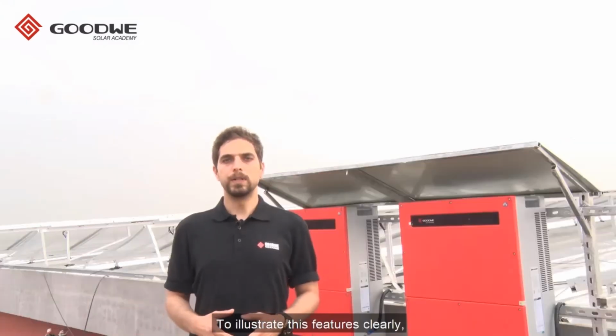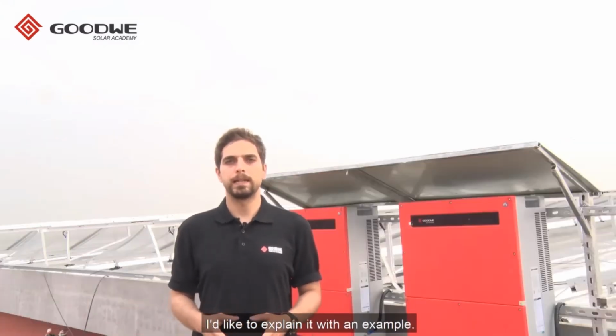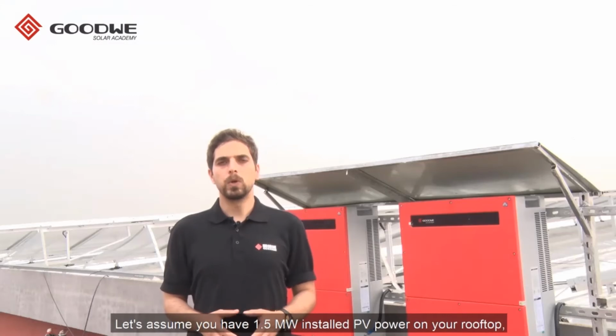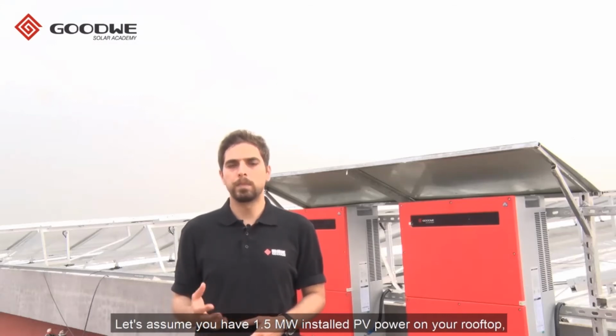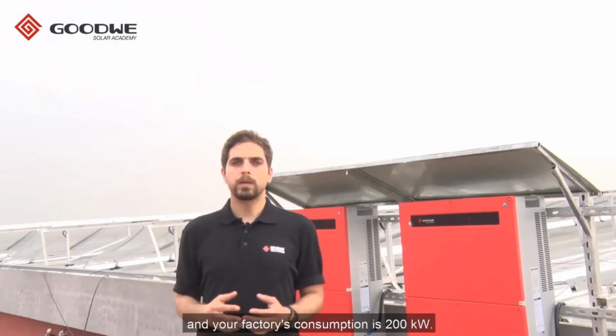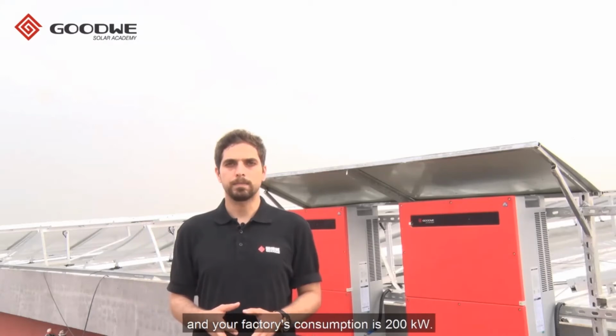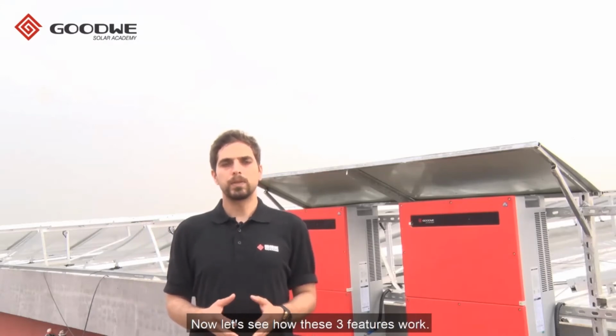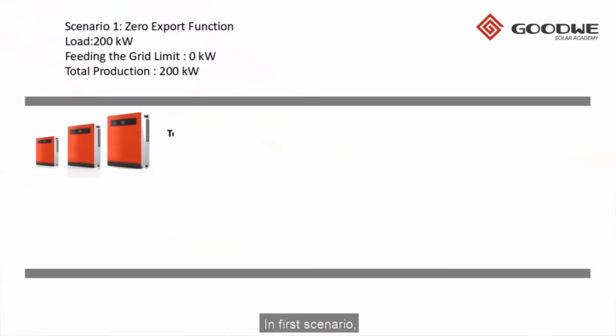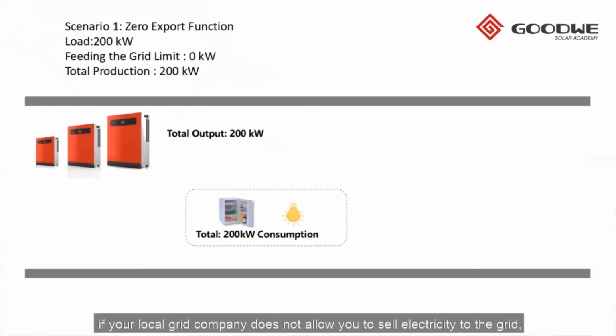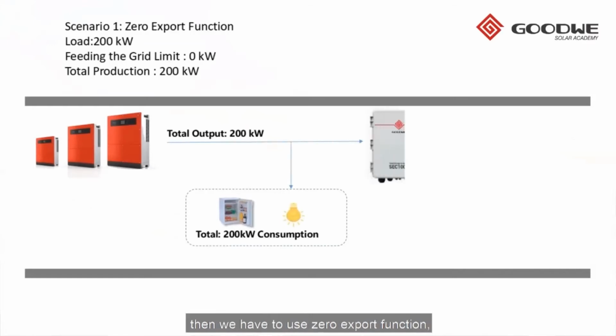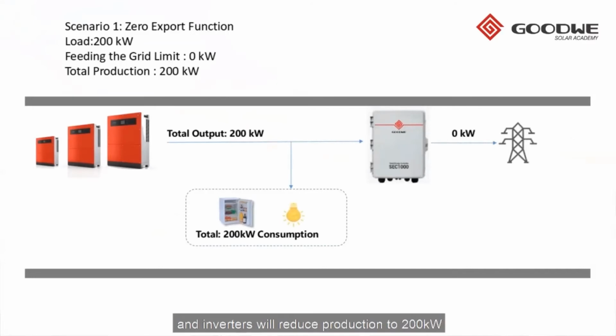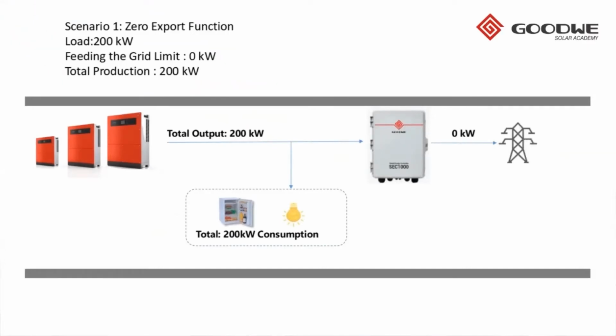To illustrate these features clearly, I would like to explain with an example. Let's assume you have 1.5 megawatts installed PV power on your rooftop and your factory's consumption is 200 kilowatts. Now let's see how these three features work. In first scenario, if your local grid company does not allow you to sell electricity to the grid, then we have to use zero export function.